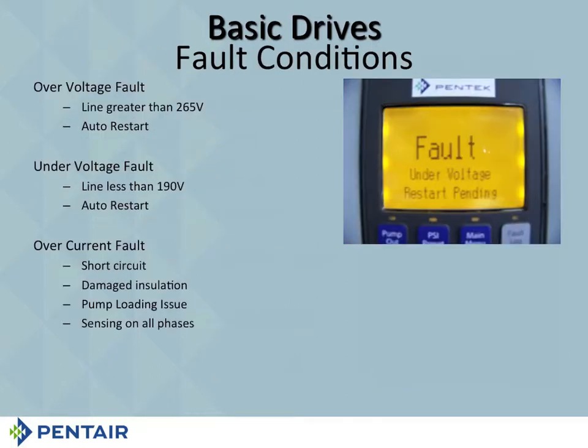Fault conditions. You're going to notice the first two there are under voltage and over voltage. If you look on the screen, it says fault, and then right below it, it tells you what the fault is, and right below that, it says restart pending. If you're getting a voltage fault, do not hit reset, because the bottom line is, as soon as you turn it back on, unless it's already fixed itself, it's just going to fault out again. So wait for the voltage to come back up. When the voltage comes back up, it will turn back on automatically. No, it won't forget anything. It'll remember everything you told it, so you don't have to worry about that, okay? But those are auto restart.